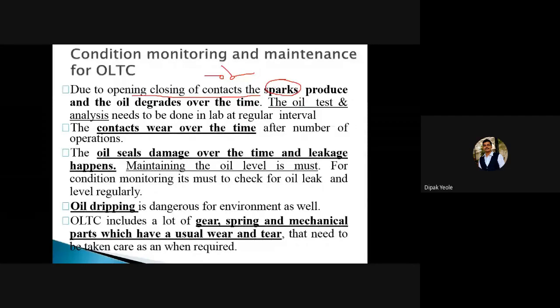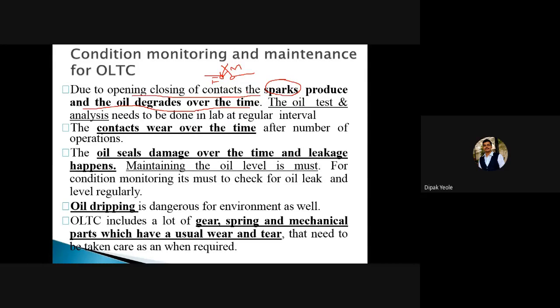How does that spark occur? Because there is a fixed contact and a moving contact. Whenever you close the moving contact to the fixed contact, there is obviously a spark to be observed. This spark is produced and the oil degrades over time. As we know, to minimize this spark we have to use oil, which is nothing but the insulating material. As continuous sparking is available, or continuous on-off application is available, because of this the oil degrades over time. We know that degradation means losing its property. The oil test and analysis needs to be done in the lab at regular intervals — that is nothing but condition monitoring.